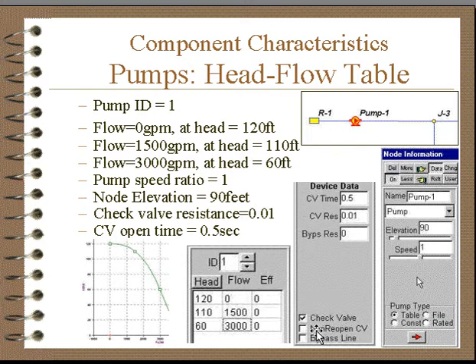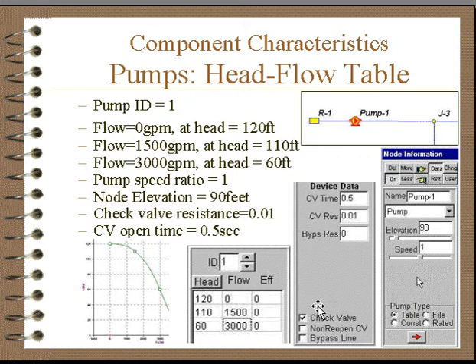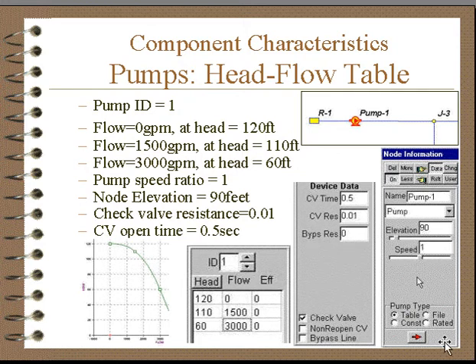They can have a non-reopening check valve, which will allow the check valve to activate just once and then it stays shut. And a bypass line, which will allow flow to bypass the pump if the suction pressure exceeds the discharge pressure. To specify these devices, we check these boxes and provide the corresponding data in the location shown.